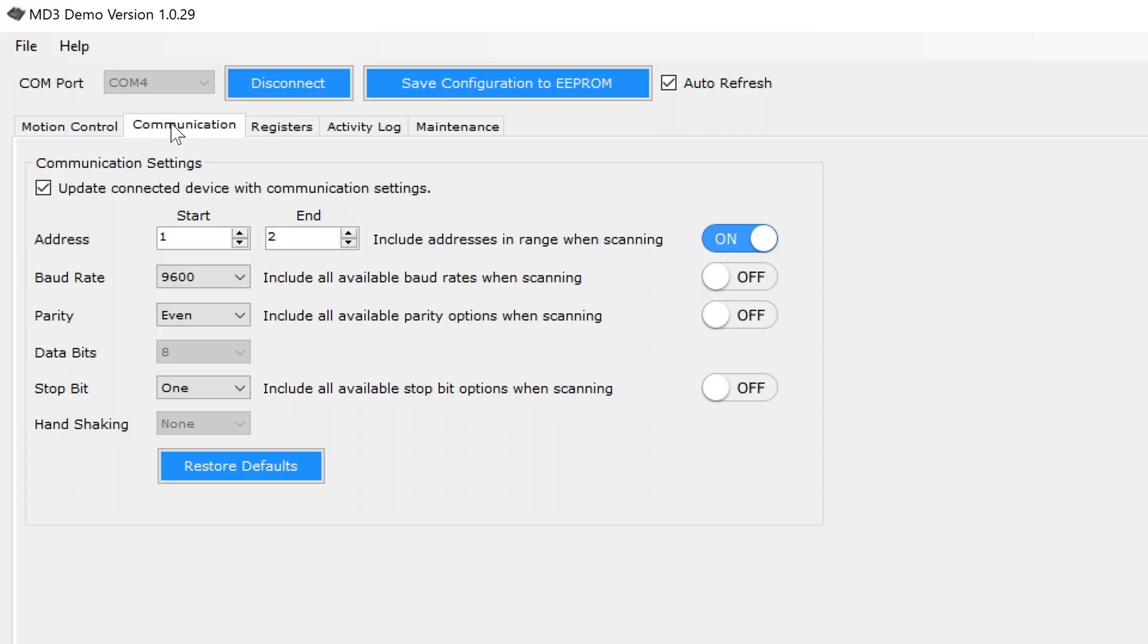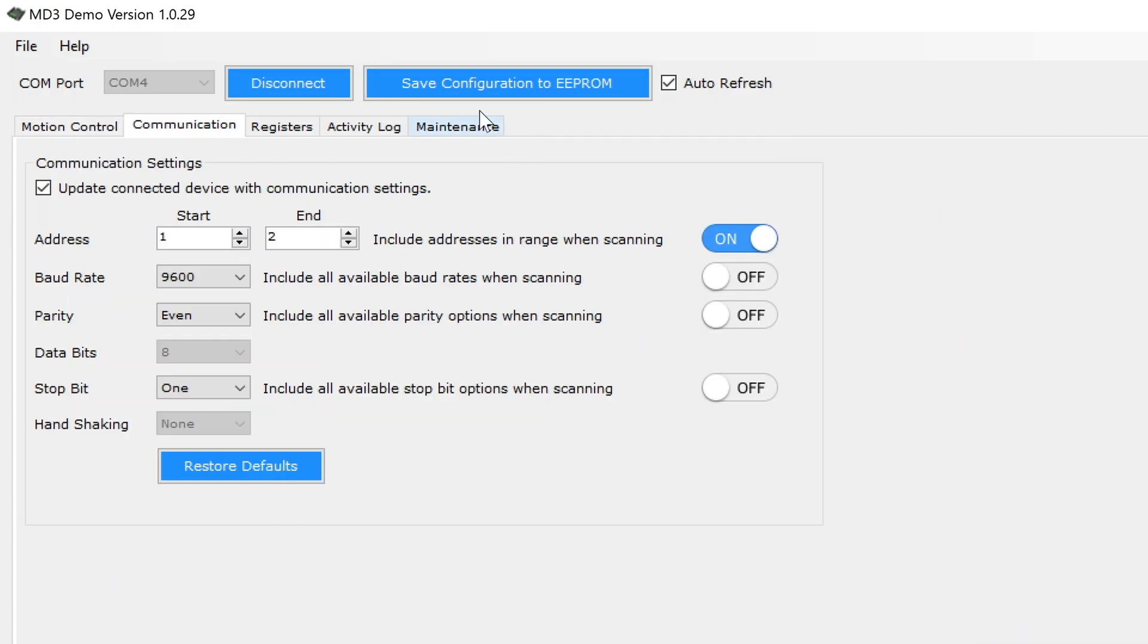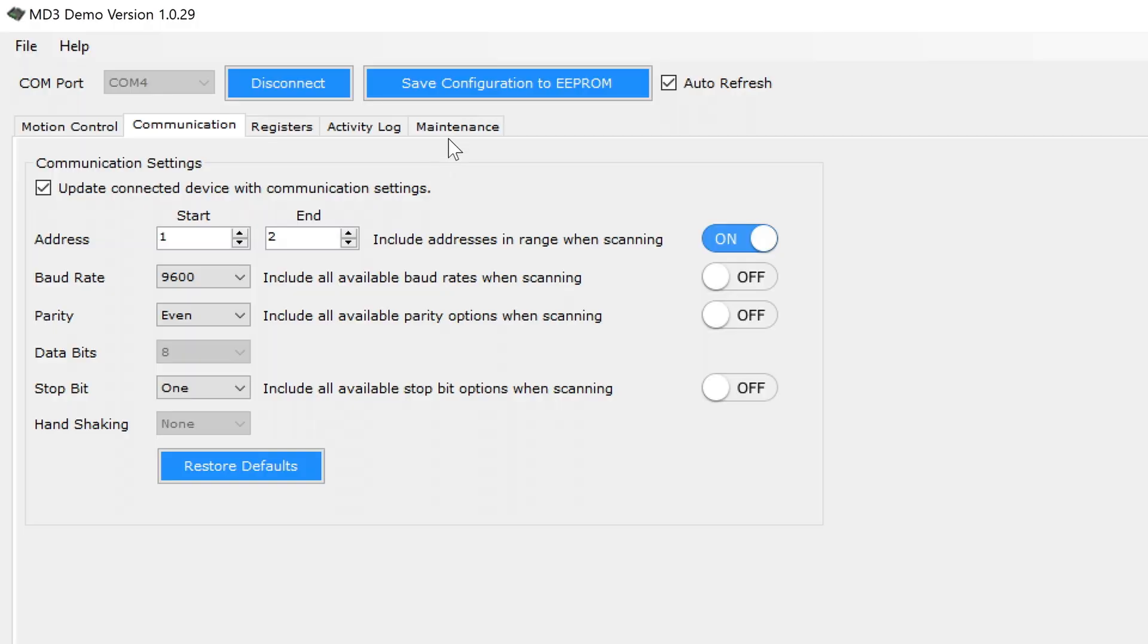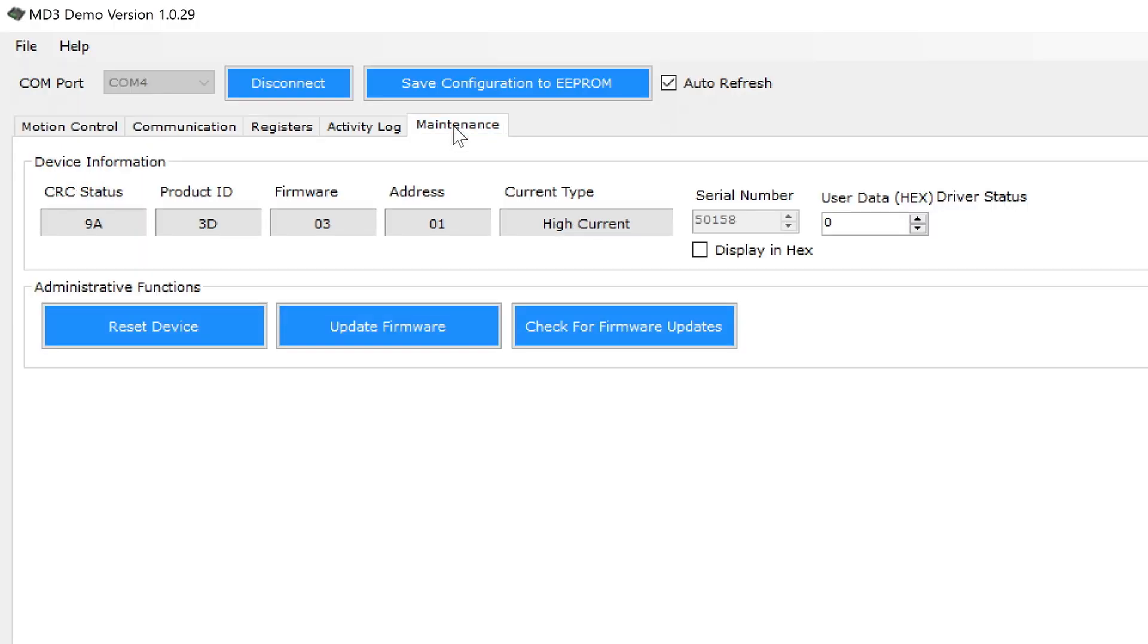Any changes you make will modify the internal RAM registers of the MD3 and take effect immediately, but they will not be saved to non-volatile EEPROM on the MD3 until the save configuration to EEPROM button is pressed. If the current configuration is not wanted, the unit can be power cycled to reload the previous settings from EEPROM, or you can click the reset device button on the maintenance tab.